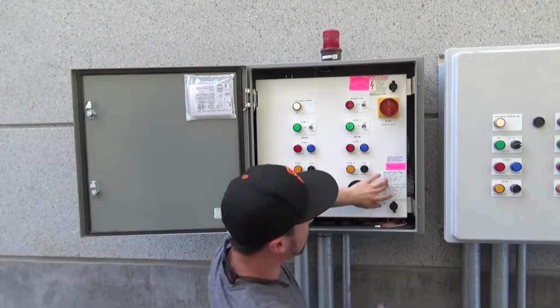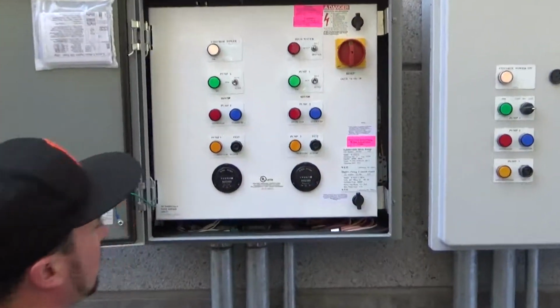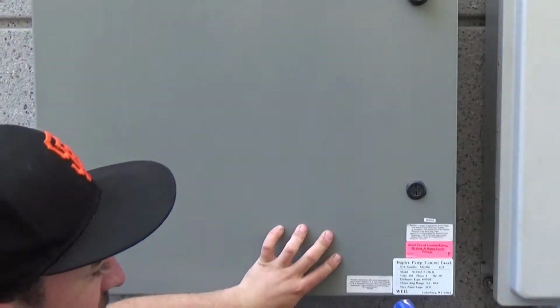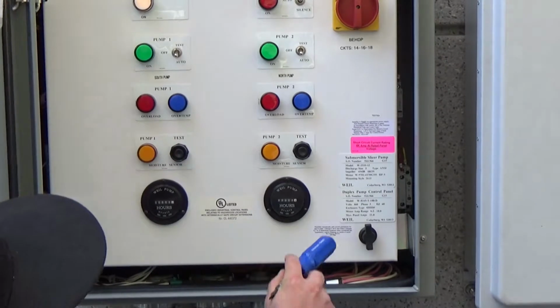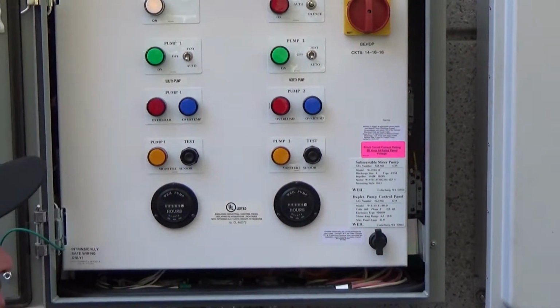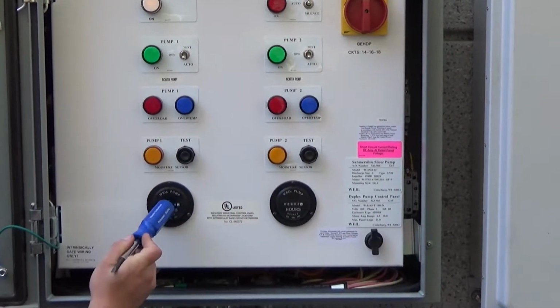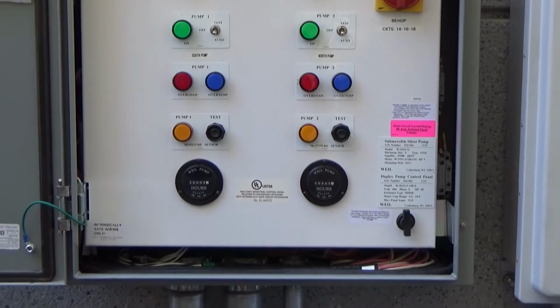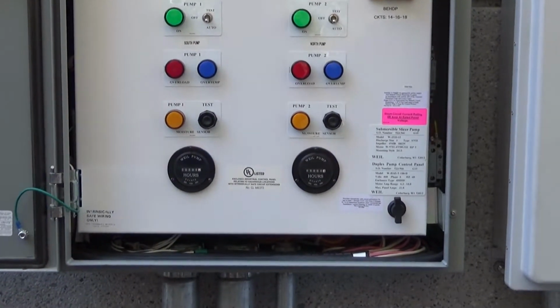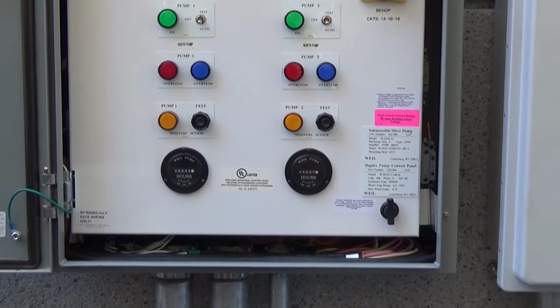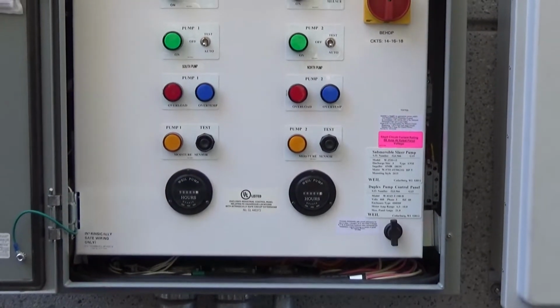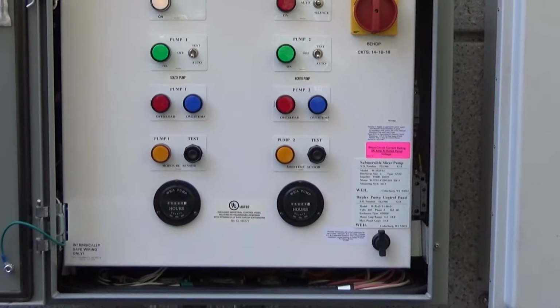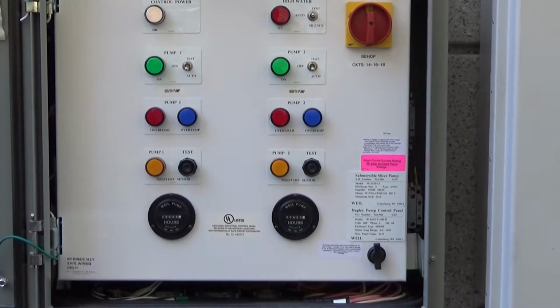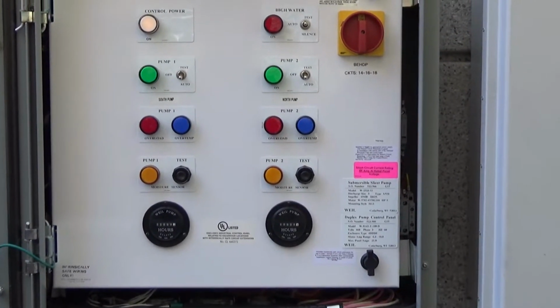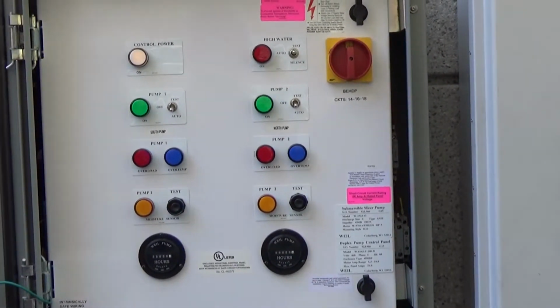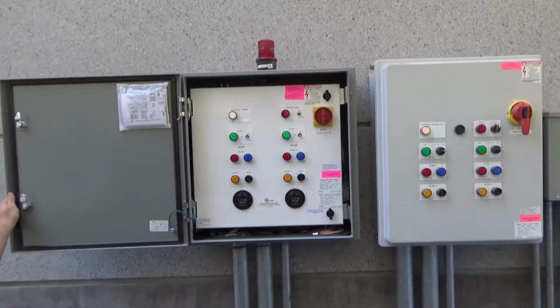Also more information on the pump and the system. This one only has the panel sticker. This one is going to give you the pump information also, and run hours, which is nice. At least you guys get to know how often that pump runs, or how much it's run, I should say. That one doesn't have that. So again, super basic. 2 pumps, floats. Float makes, pump comes on. Float breaks, pump shuts off.